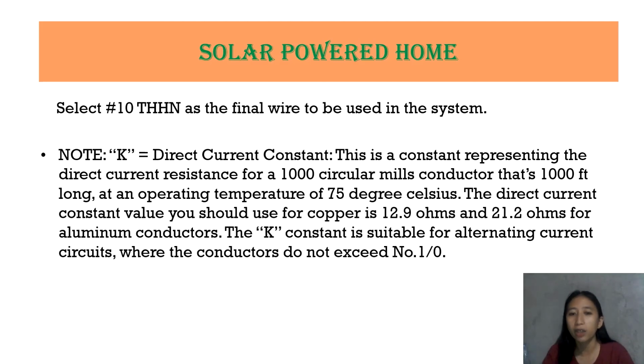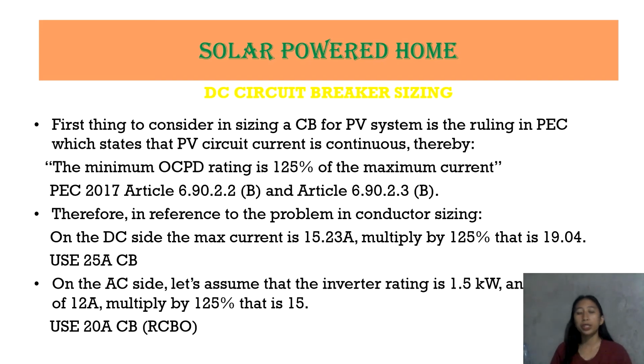So, the K constant is suitable for alternating current circuits where the conductors do not exceed number 1 over 0. Okay, so let's proceed on our DC circuit breaker sizing. Okay, there are things to consider para sa ating breaker sizing. First thing to consider in sizing a CB for a photovoltaic system is the ruling in PEC, which states that PV circuit current is continuous. Okay, thereby, the minimum OCP rating is 125% of the maximum current.